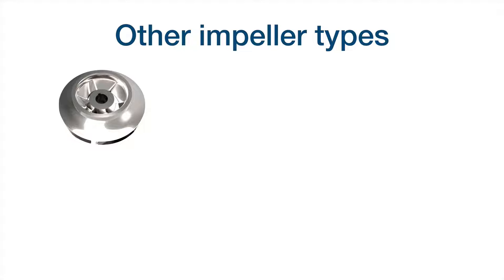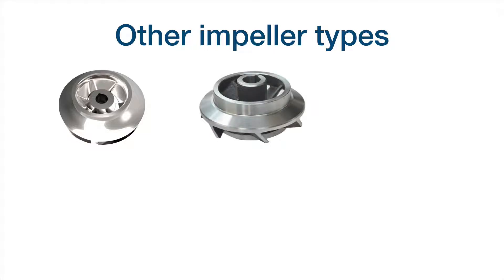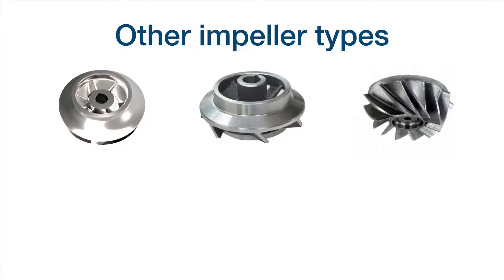Other impeller types: this is a Francis impeller — a closed Francis impeller — which is a mixed-flow type impeller. This is also a mixed-flow impeller, but semi-open. This one is also semi-open but slightly different from the previous one — it is tailor-made, an engineered pump where the blades are welded to the hub. Normally this pump is used for special applications, for example in power plants for circulating water pumps, delivering high flow rates and low heads.